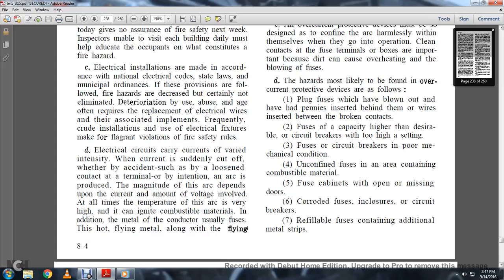Fuses with capacities higher than desired, and circuit breakers with too high a setting. Fuses and circuit breakers in poor mechanical condition. Unconfined fuses in an area containing combustible material. Fuse cabinets that are open or have missing doors. Corroded fuse enclosures and circuit breakers.